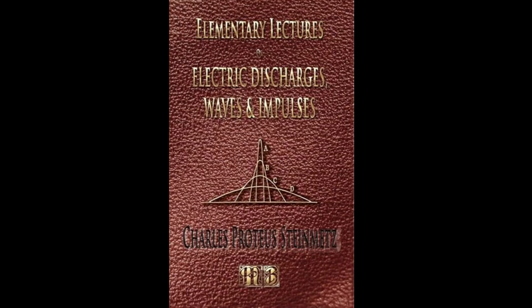Figure 25 shows a single-phase short circuit of a quarter-phase alternator. The upper wave is the voltage of the phase which is not short-circuited, and shows the increase and distortion resulting from the double-frequency pulsation of the armature reaction.